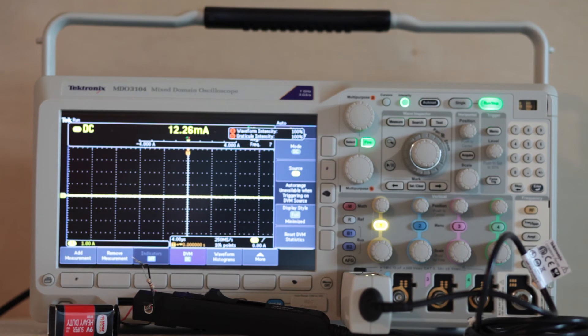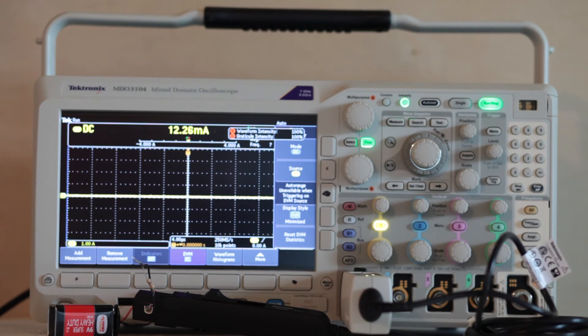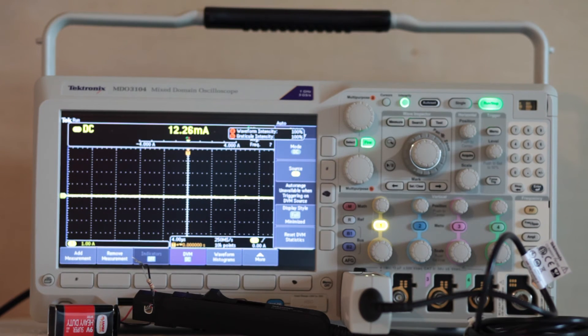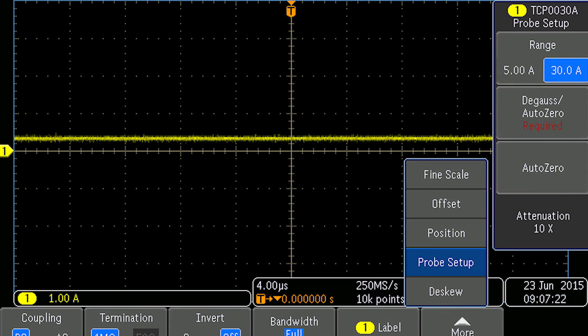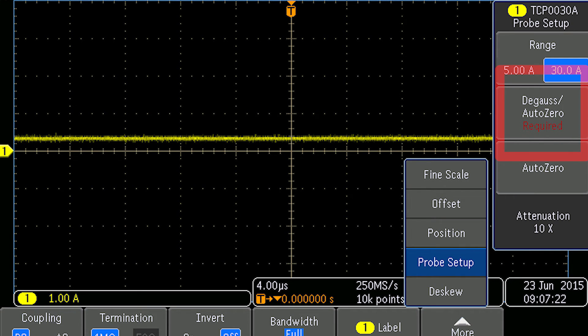Then, any measurements will be invalid. When connected to the oscilloscope, a window opens in the display, and it will alert you to degaussing. Simply press the degauss button on the probe, and the residual magnetism is eliminated.